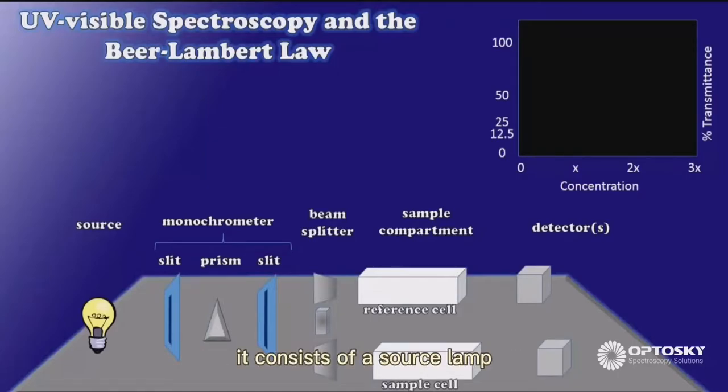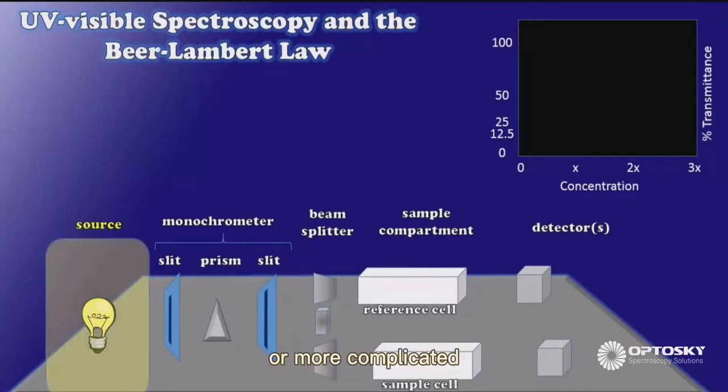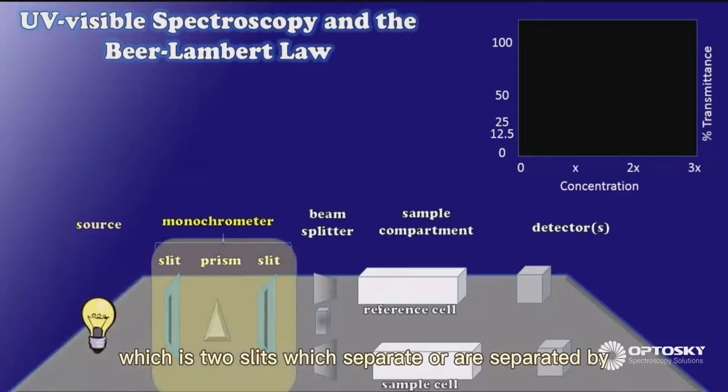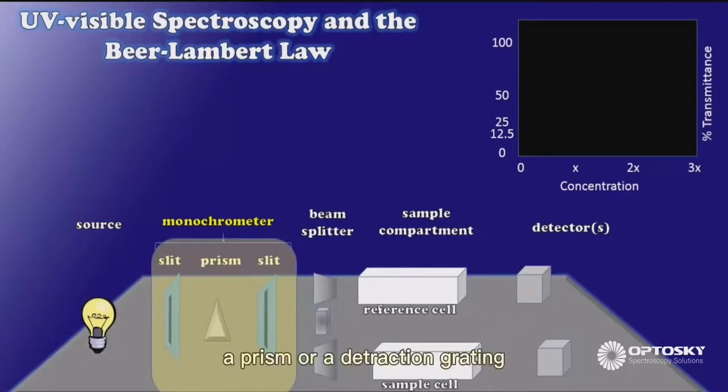It consists of a source lamp, which is something as simple as the headlamp from a motor scooter, or more complicated, like a deuterium lamp or xenon arc lamp. The next device in line is what's known as a monochrometer, which is two slits which are separated by a prism or a diffraction grating.